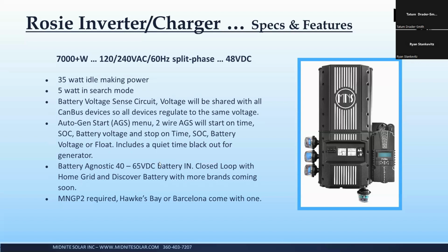We talked about the AGS. Full functionality starts on voltage, time, state of charge. There are quiet time, blackout windows. It has the ability to stop on any of those, as well as like going to float. And you can start on one and stop on another. It's very flexible in how you can program that if there's a reason to. There's also load shedding. If the load is too big, we can shed the load over and start to generate. There's a lot of cool stuff there. Battery agnostic. We really don't care what you use for a battery, as long as it's between 40 and 65 volts. And as I mentioned, closed loop coming with home grid discover. I think there's a Renogy battery, and I was thinking maybe simplify, but I'm drawing a blank on some of those names.